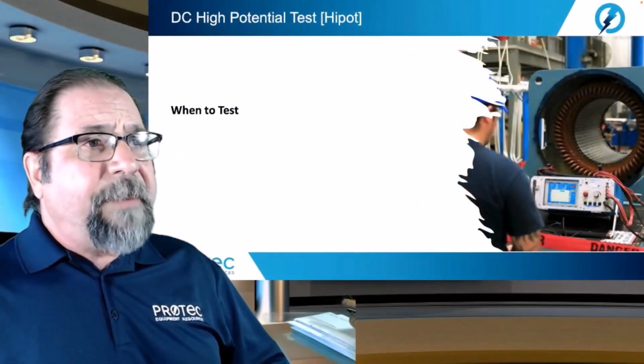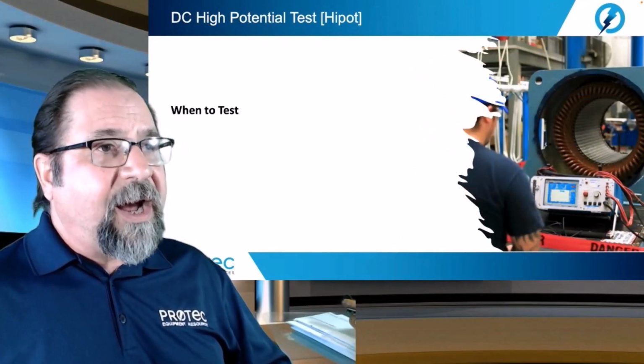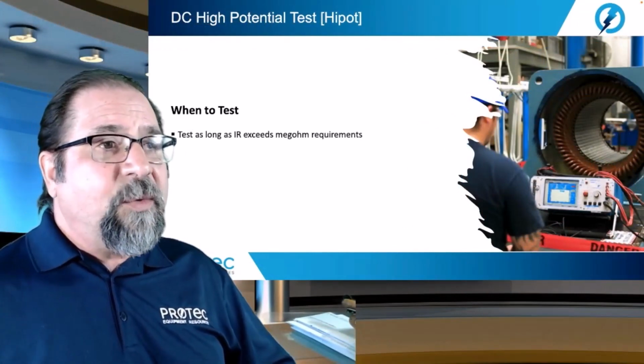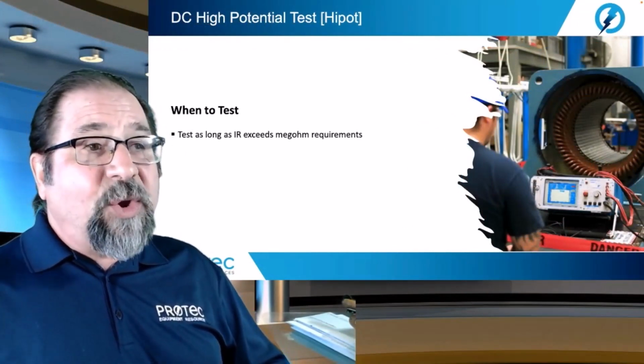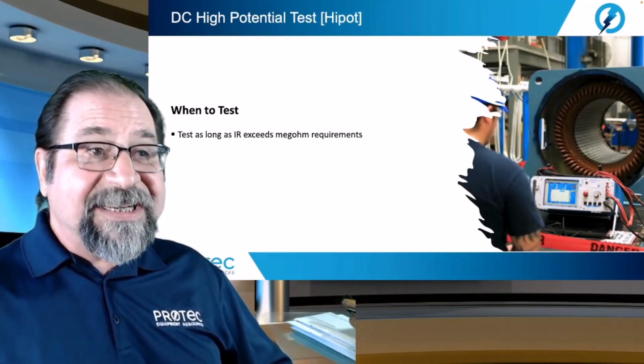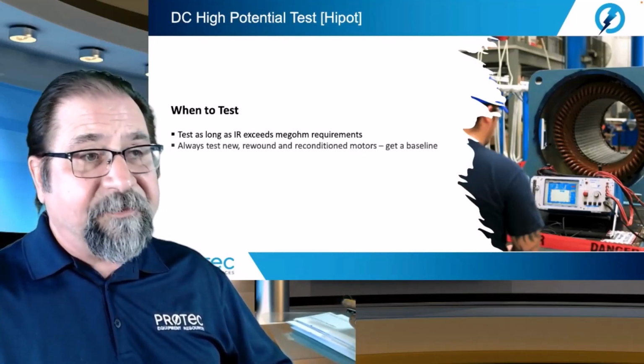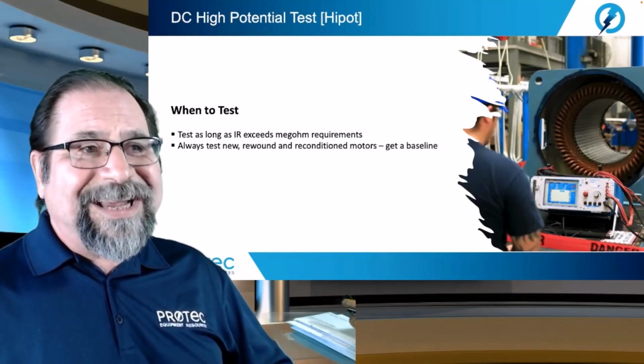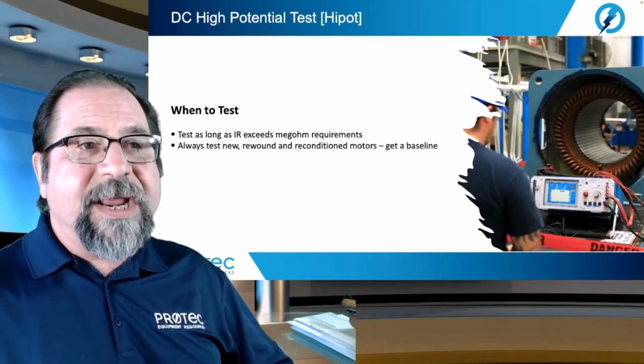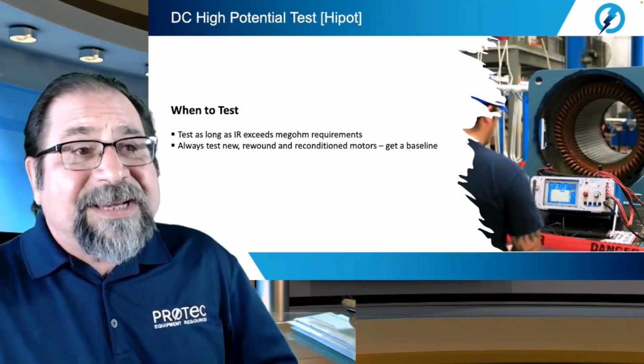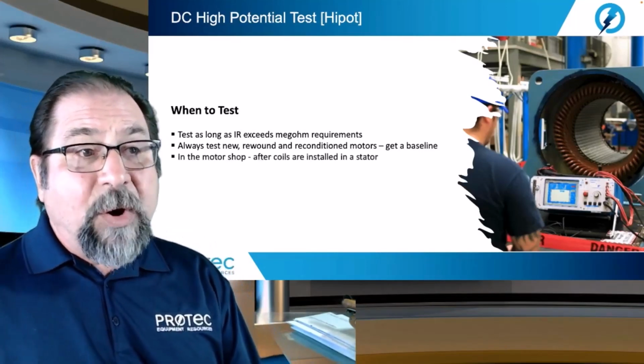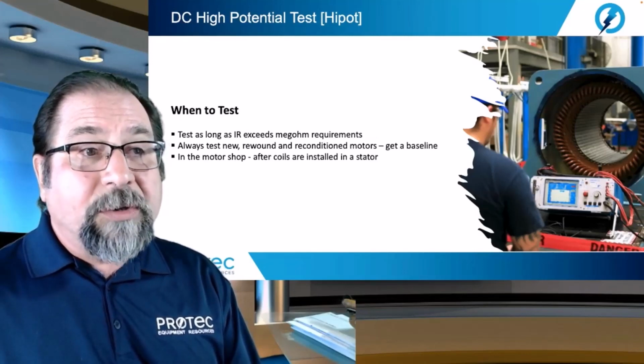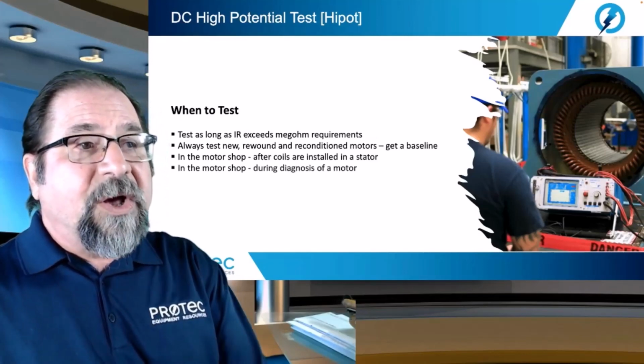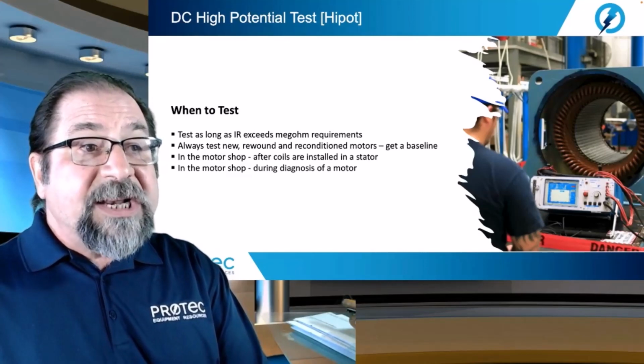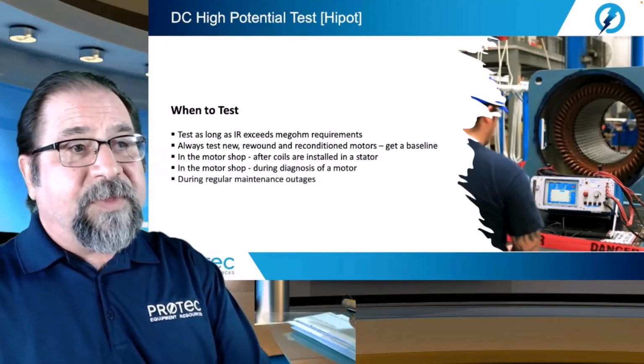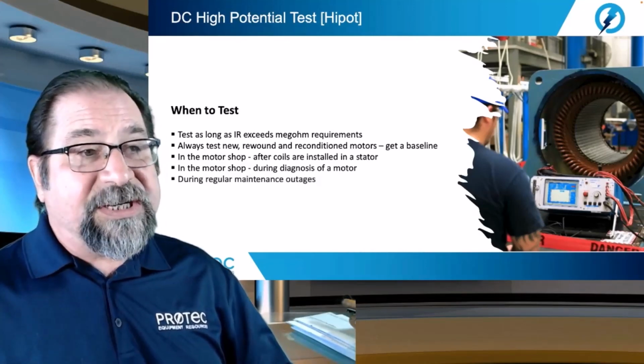All right, let's talk about when to perform a high potential test. Well, we can test as long as the insulation resistance exceeds megohm requirements. And always test new, rewound, and reconditioned motors. Get yourself a baseline. In the motor shop, after the coils are installed in a stator. Also in a motor shop, during diagnosis of a motor. During regular maintenance outages.